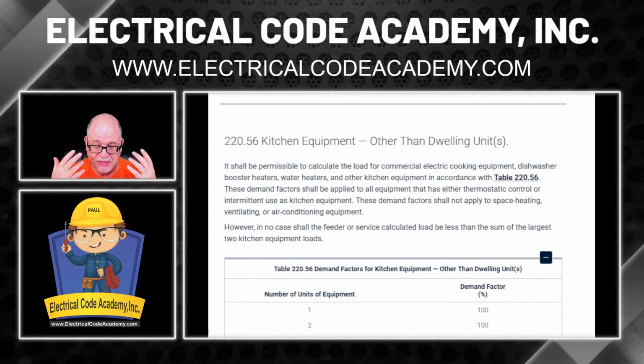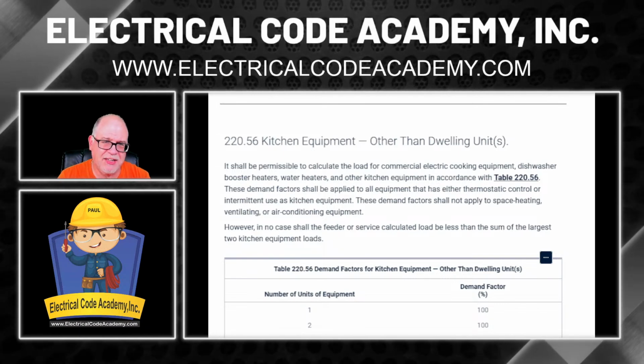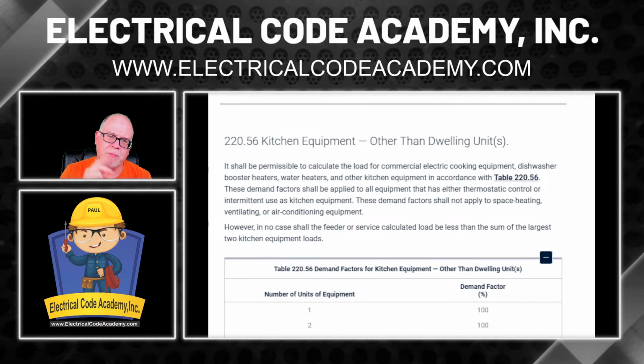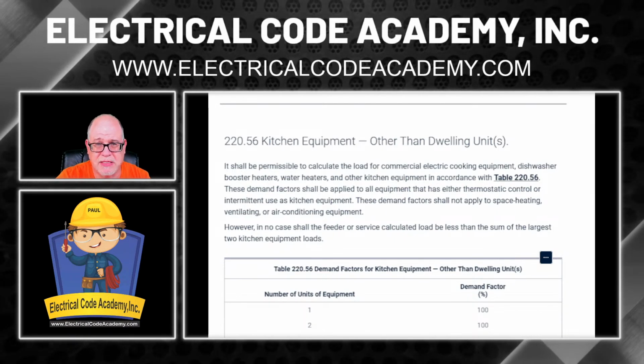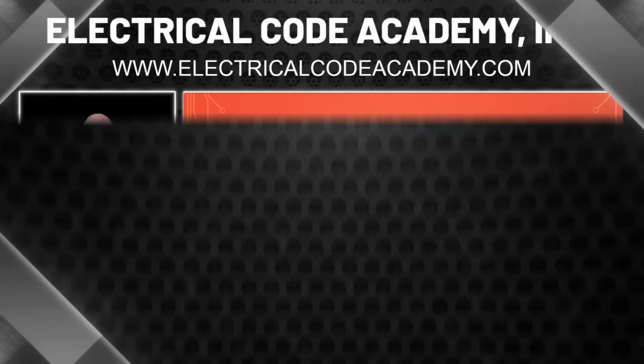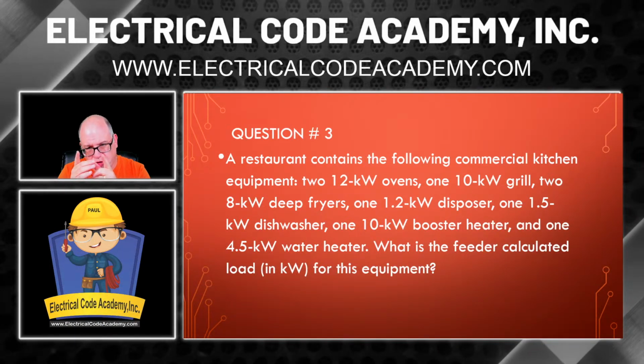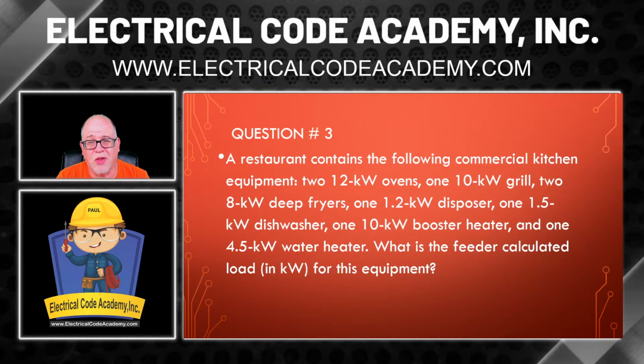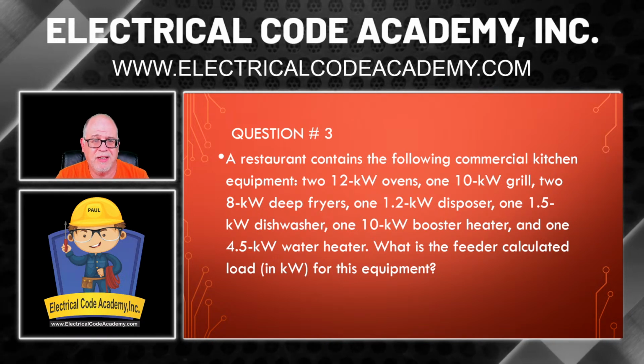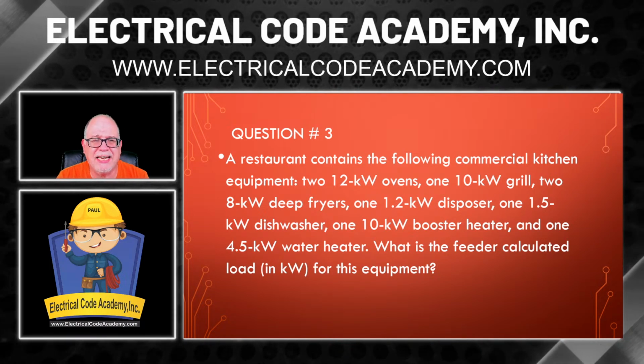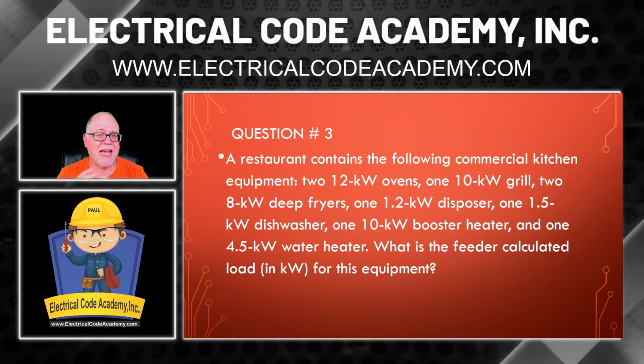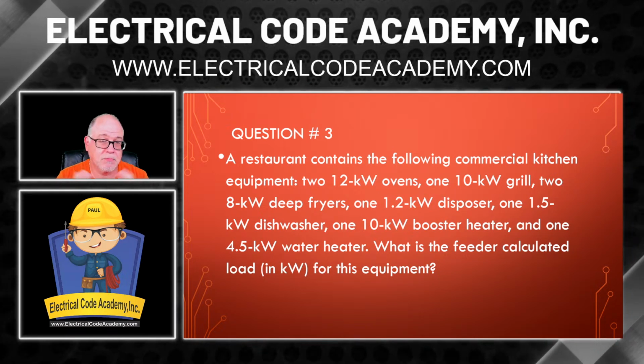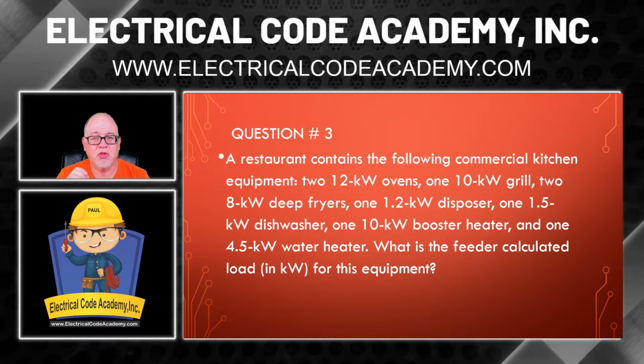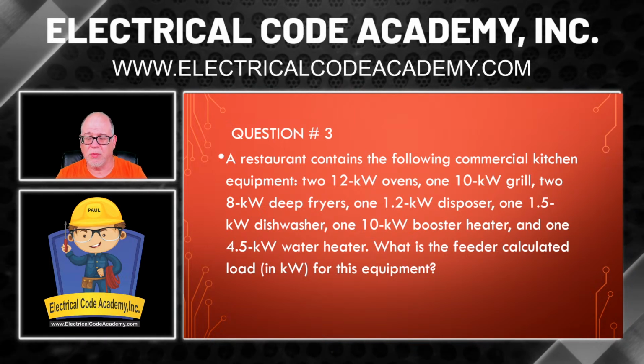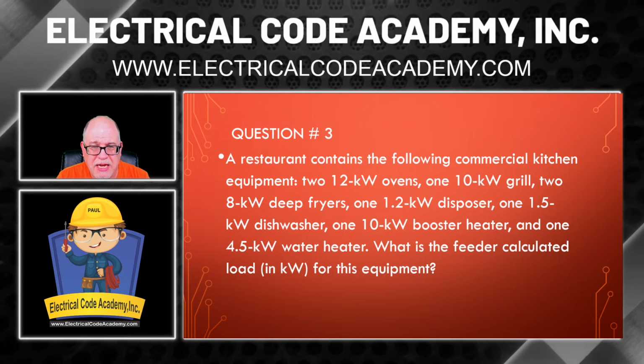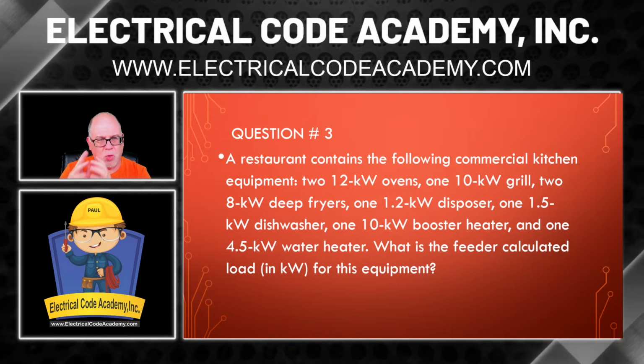Now, we added everything up, but when you looked at that list again, what were the two largest pieces of equipment? And I'll go back so you can see it. So the two 12 kW ovens were the two largest pieces of equipment here. Now together, that's 24 kW. So we already know that it can't be less than 24 kW in our equation. So with that in our pocket, we can look at the questions on the exam, and we know why they're asking this type of question.